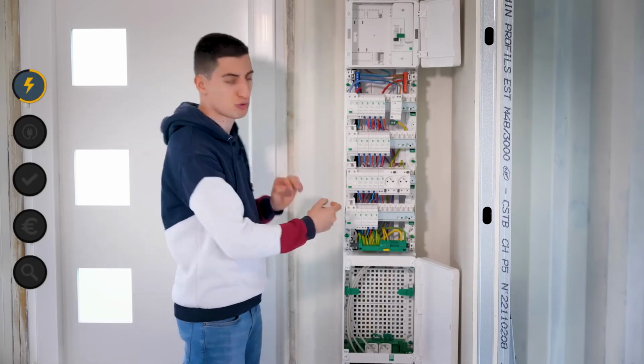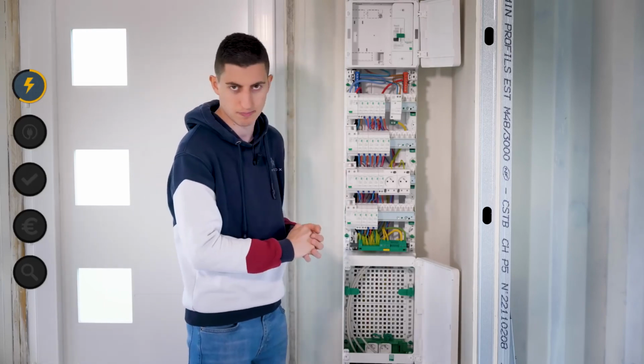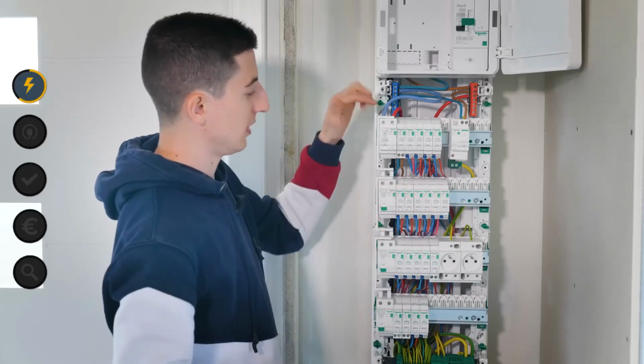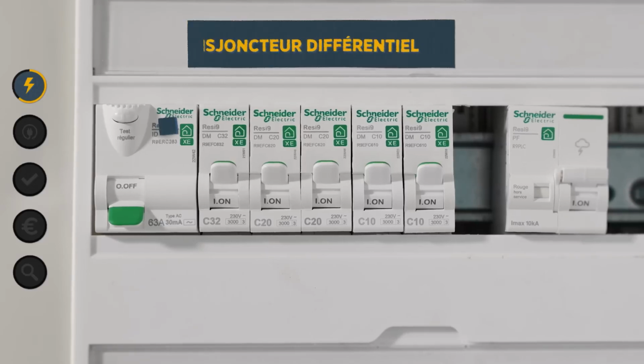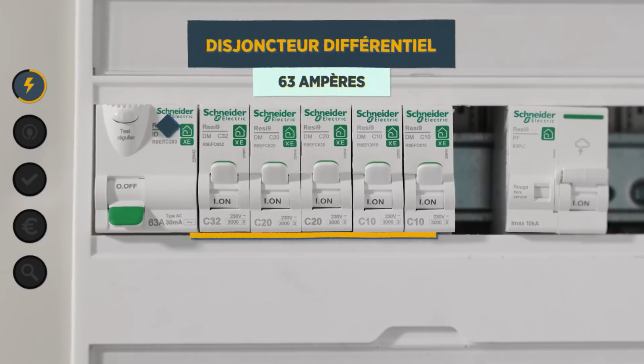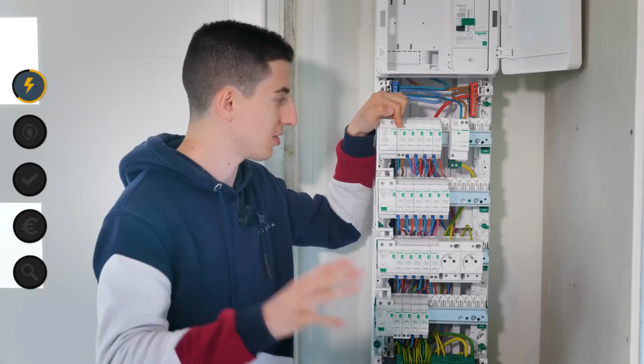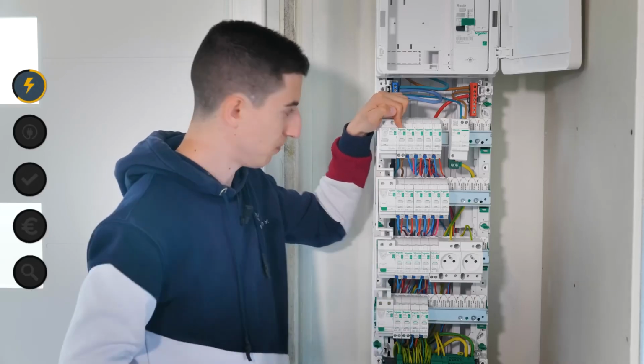I'll give you an example on one line, you'll understand much more easily. Let's take the first line of my electrical panel. We have a differential of 63 amps. On it, I have a 32 amp breaker for my heat pump. As I told you before, the heat pump is an exception, so we don't divide by 2.